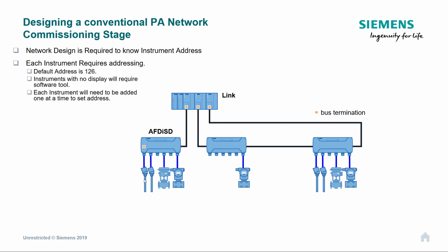The other issue you have, if you have simple Profibus PA devices, maybe a simple temperature probe or something like a VA meter, a low-cost flow meter on Profibus PA, these have no displays, and some of them have no dip switches. So you do need software to configure the address of those devices. Now the problem is if you've got these already wired up and powered up, you're going to have to disconnect all of the ones that you're not sure about, connect one at a time here, for instance, and set the address, and then move on to the next one. If you've got a small to average job with 50 odd instruments on, that could take a good day of commissioning time, just getting the addresses and the network up and running.